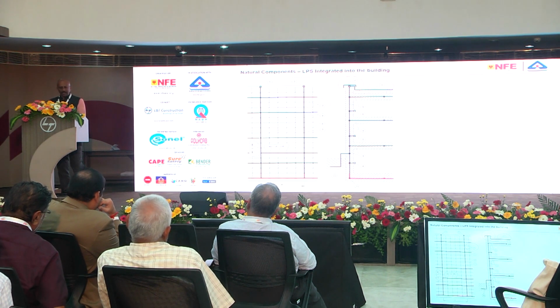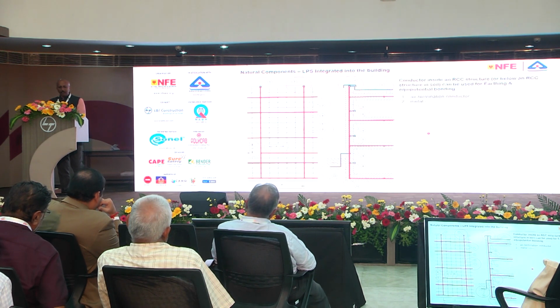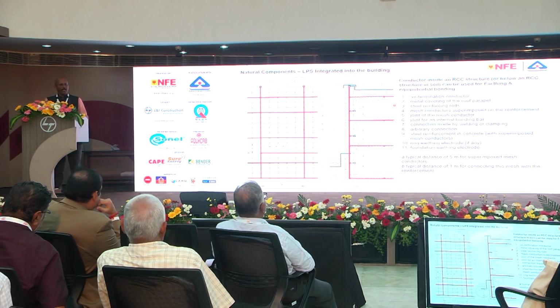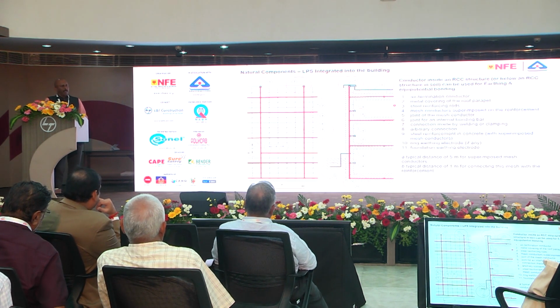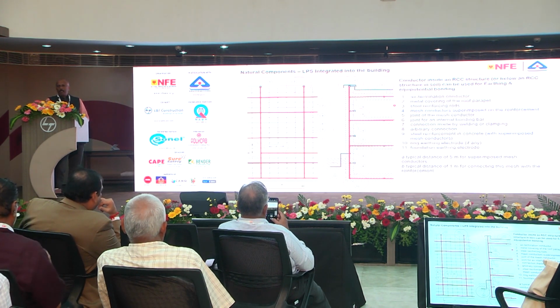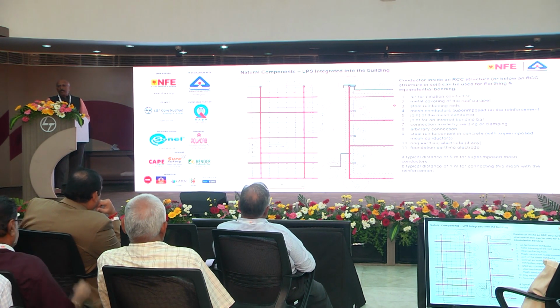the objective is achieved. In the standard, you can find a picture with these explanations: air termination, mesh conductors and all. Basically, what we are doing is, the air terminal at the top of the building is connected to the rebar, and now your structure is made into a down conductor.